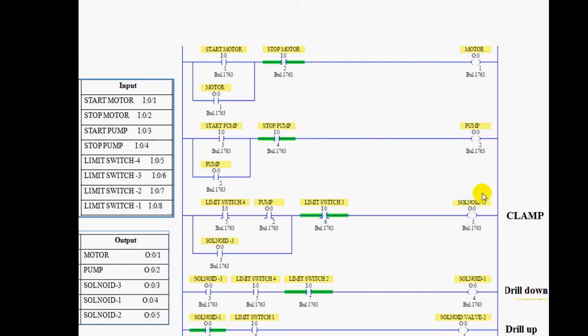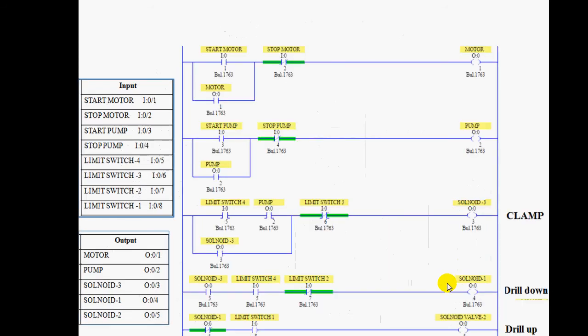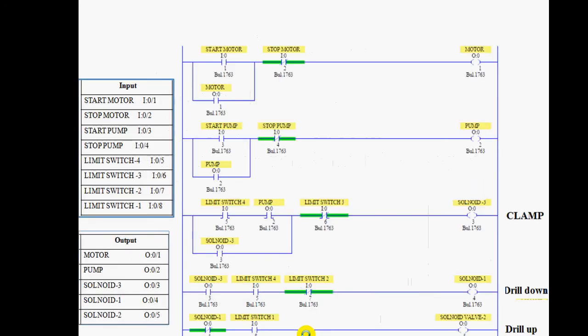When solenoid three is on and limit switch four is on, solenoid one activates. Solenoid one means air goes from one side and the drill bit goes down. When it reaches limit switch two, it stops at the down position. Taking solenoid one and limit switch one as reference, solenoid two then activates and the drill bit goes up. This completes the ladder diagram for automatic drilling.